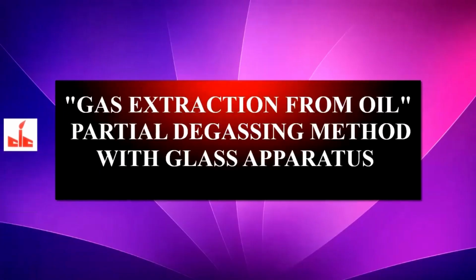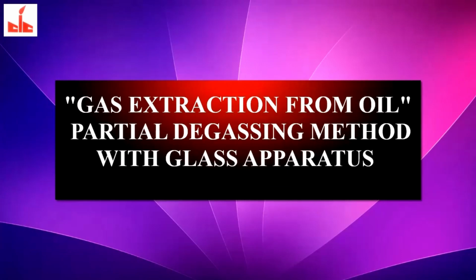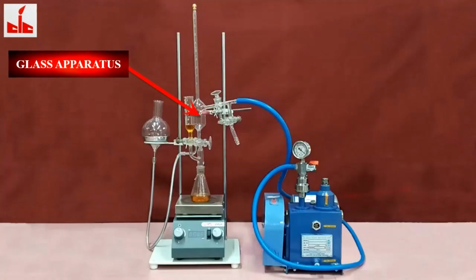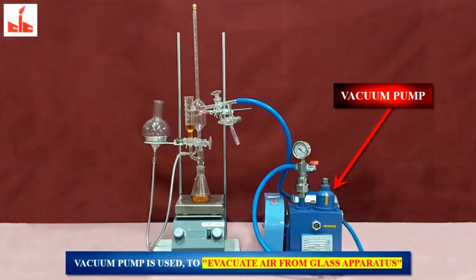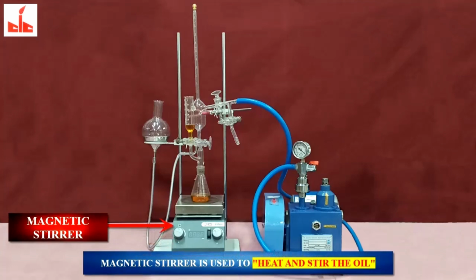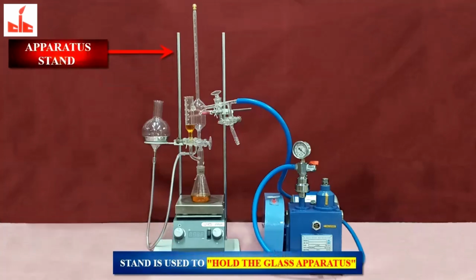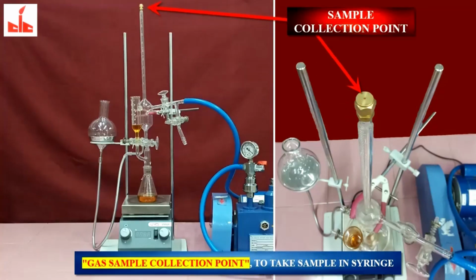Gas extraction from oil. Partial degassing method with glass apparatus. This glass apparatus is used to extract dissolved gas from transformer oil. This vacuum pump is used to evacuate air from the glass apparatus. This magnetic stirrer is used to heat and stir the oil. This stand is used to hold the glass apparatus. This is the gas sample collection point to take the sample in a syringe.